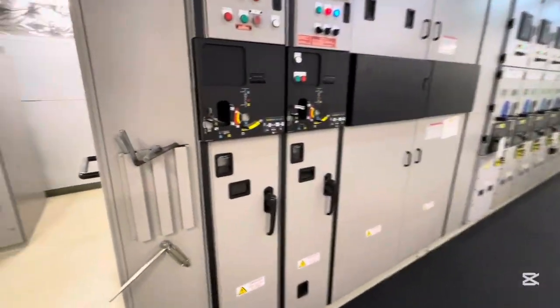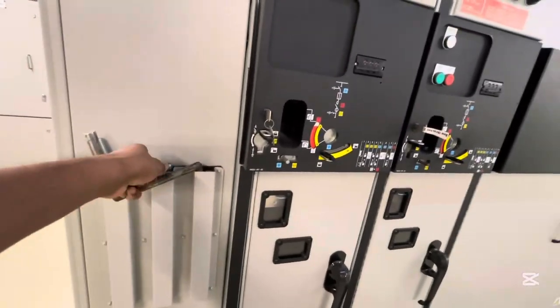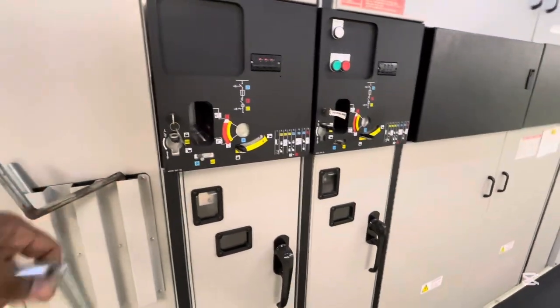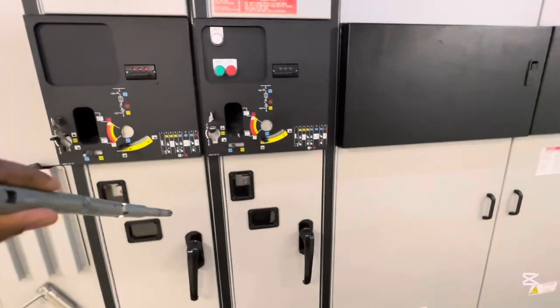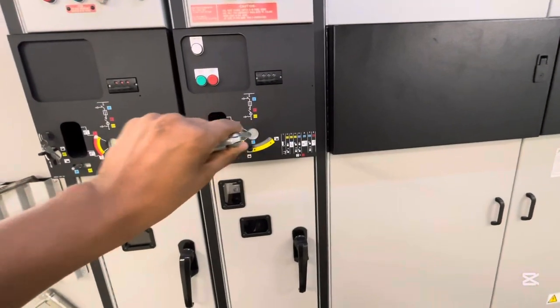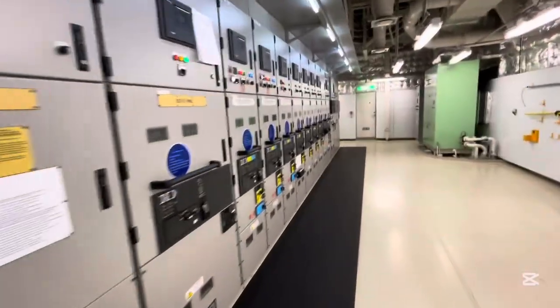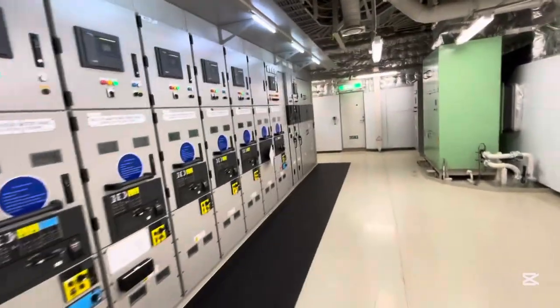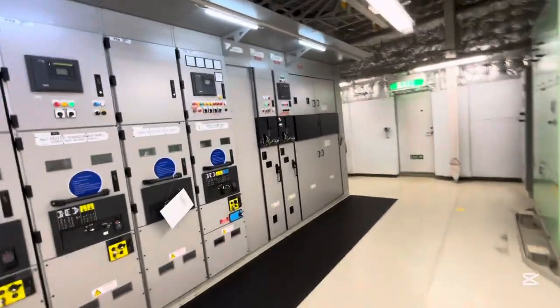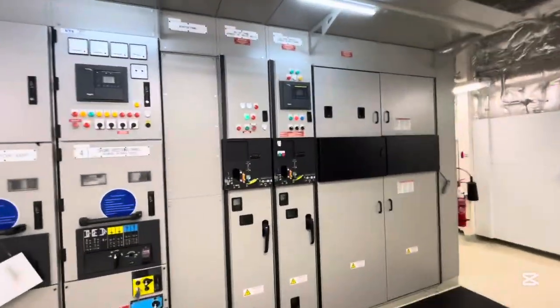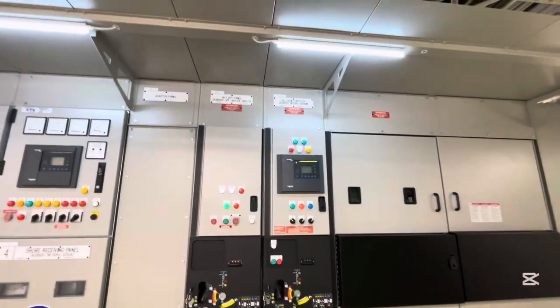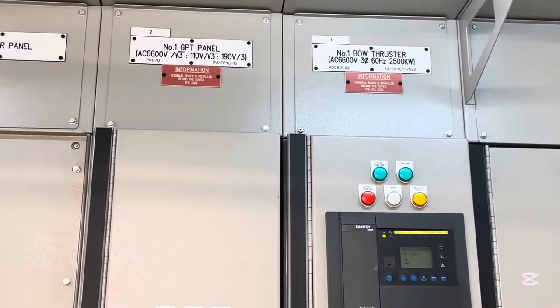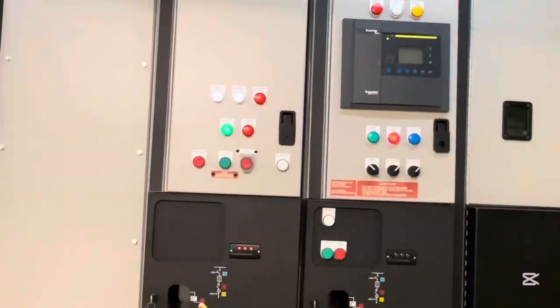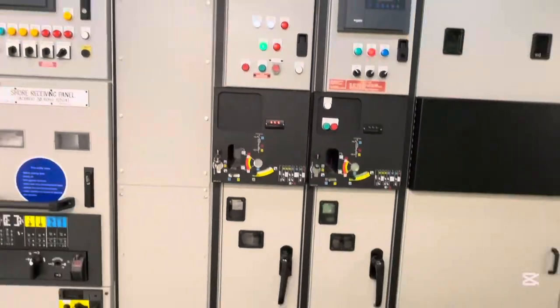Actually 110 volt is the voltage of the control circuit for this particular high voltage system. Any starter you'd normally see is like 24 volt or 220 volt, but in high voltage on my ship, it is 110 volt that is the control circuit's voltage. So in case there is a problem, a blackout, and 110 volt is not coming, then via this UPS we supply that.